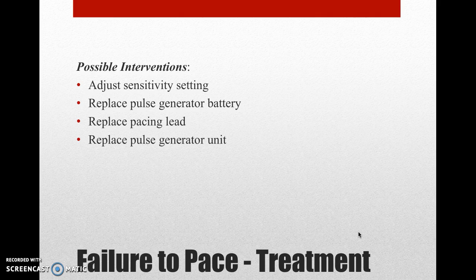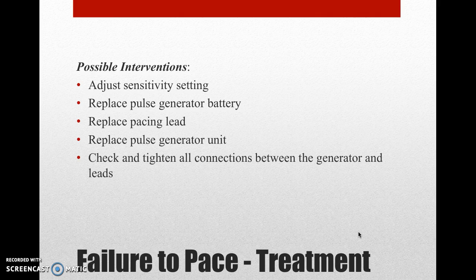The treatment for failure to pace includes the following possible interventions. Adjust the sensitivity setting. Replace the pulse generator battery. Replace the pacing lead. Replace the pulse generator unit. Check and tighten all connections between the generator and leads if you're using a temporary transvenous device.